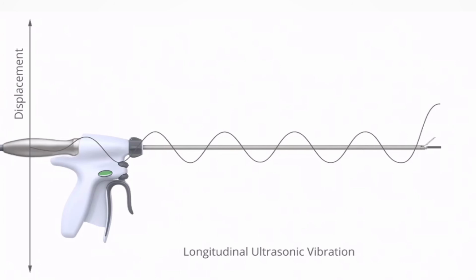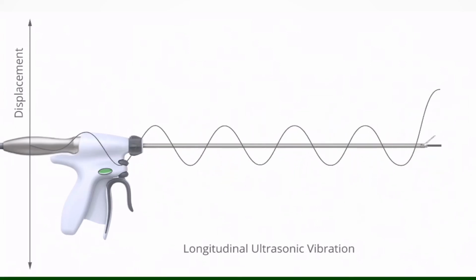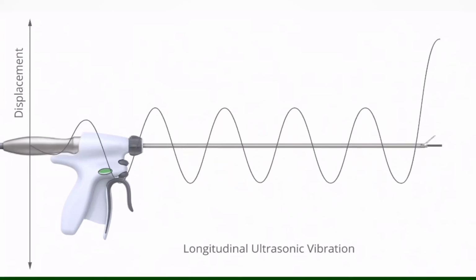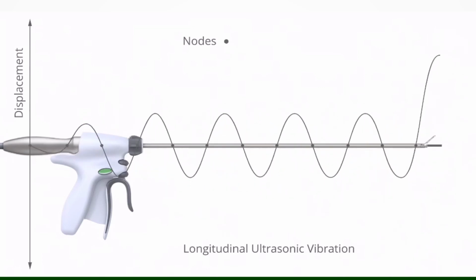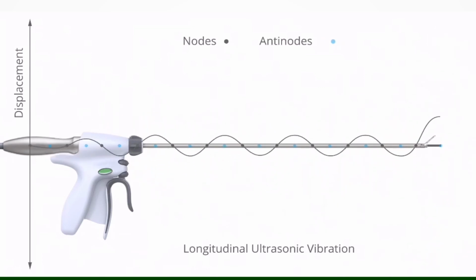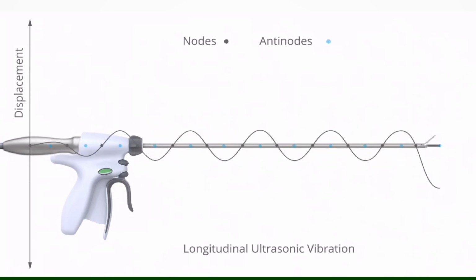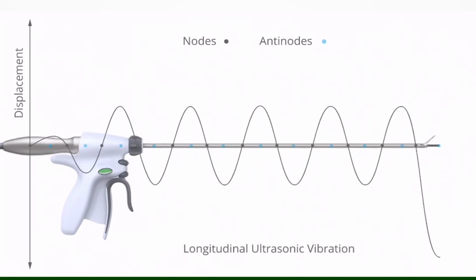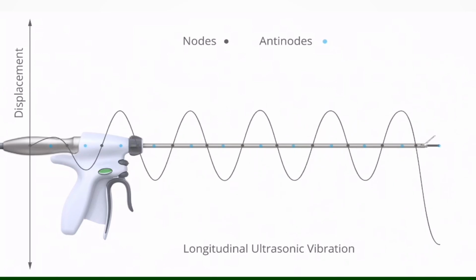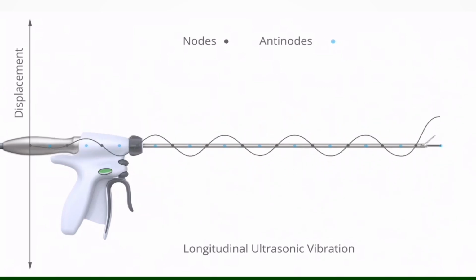Next, a common misconception is that the entire waveguide vibrates back and forth in unison. In reality, the motion is transmitted as a longitudinal vibratory wave with multiple nodes and antinodes along the length of the waveguide. Nodes are locations of minimum displacement, whereas antinodes are locations of maximum displacement. Displacement is amplified between the transducer and the blade tip by reducing the cross-sectional area of the waveguide near nodes.